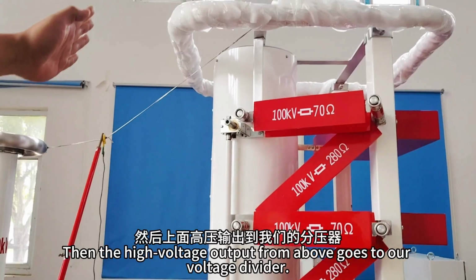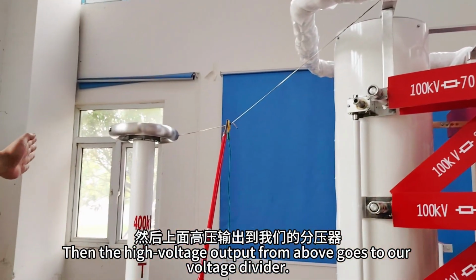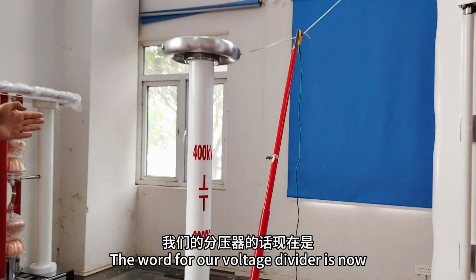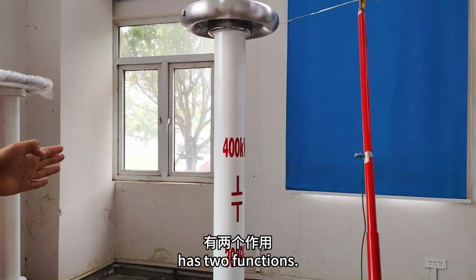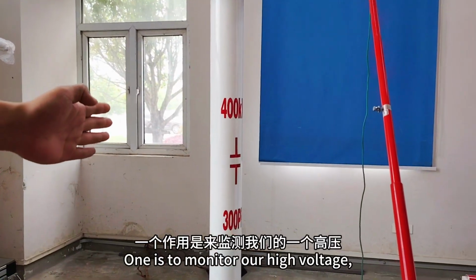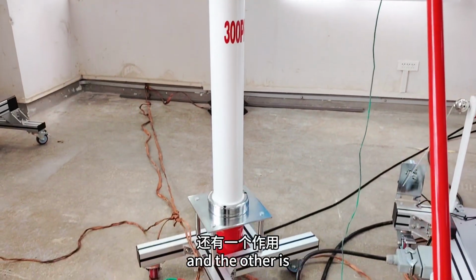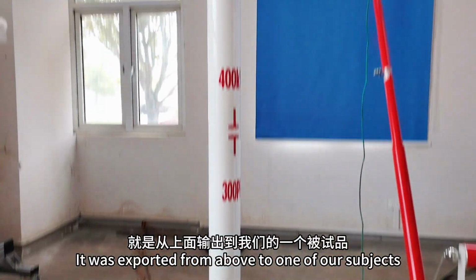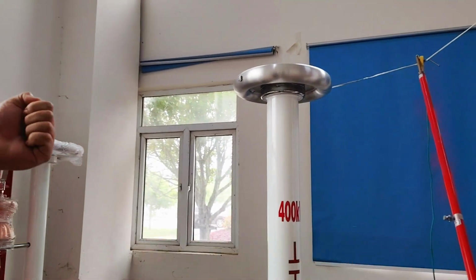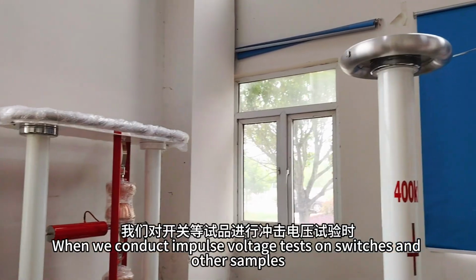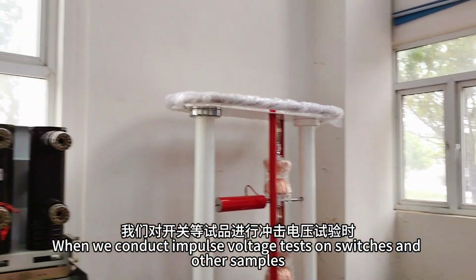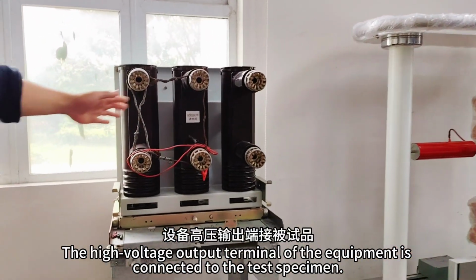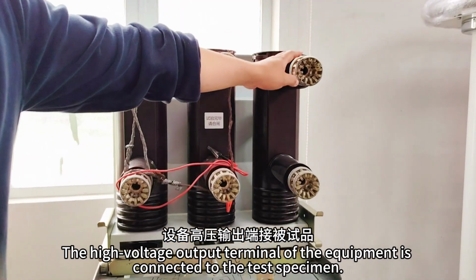The high voltage output from above goes to our voltage divider. The voltage divider has two functions: one is to monitor the high voltage, and the other is to export it to our test subject. When conducting impulse voltage tests on switches and other samples, the high voltage output terminal of the equipment is connected to the test specimen.